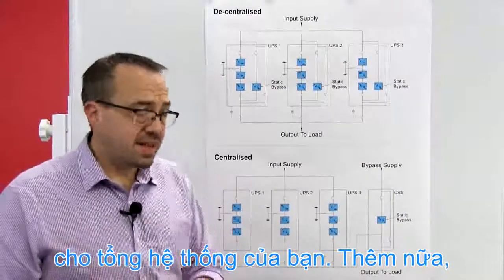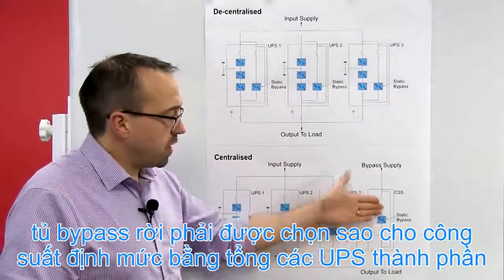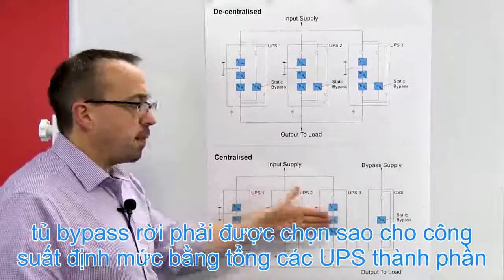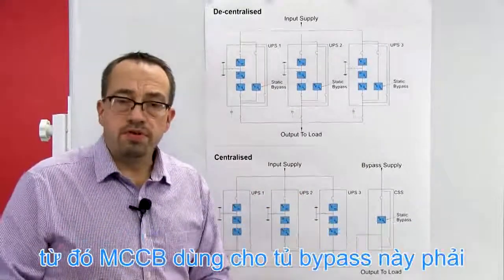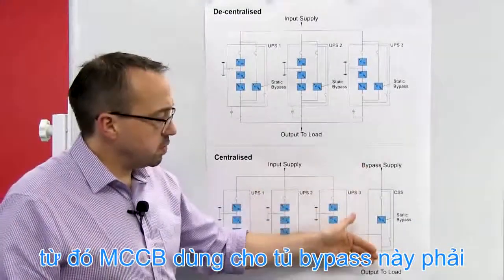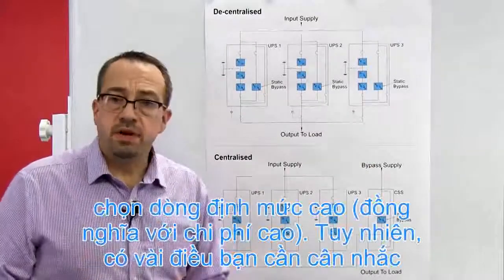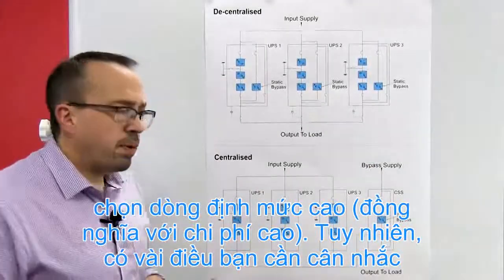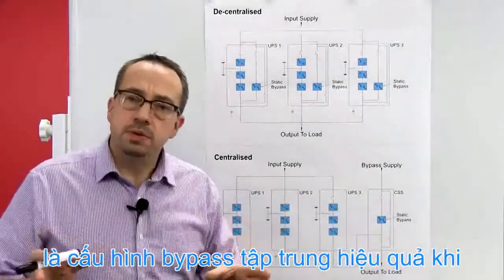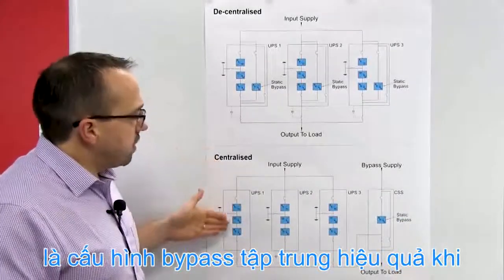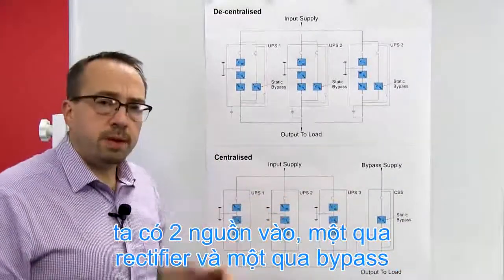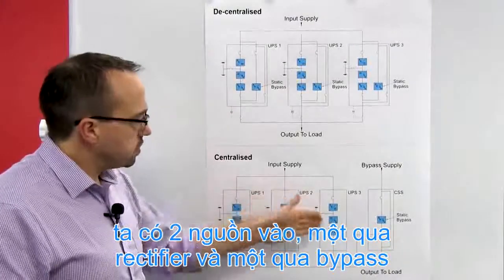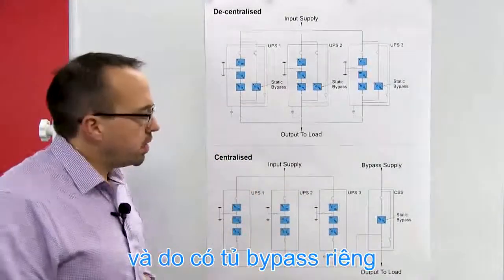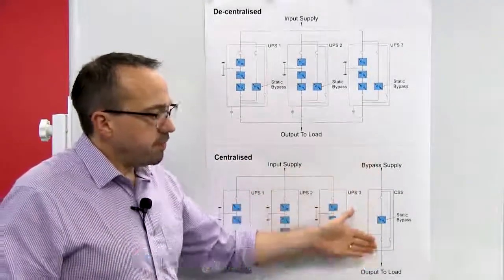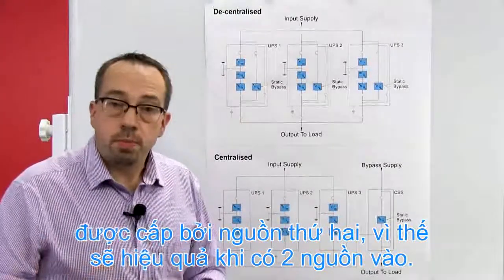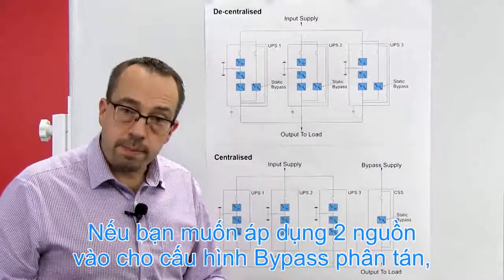And in addition to that, the bypass module would have to be rated to the maximum power connected to the output of the system, and hence the supply breakers to the bypass module could be significantly larger. However, there's something you must consider between these two systems, in that the centralized system here is effectively dual input, because you have the rectifier modules being fed from one source and you have the bypass module here being fed from another source or another breaker, and therefore it's effectively dual input.